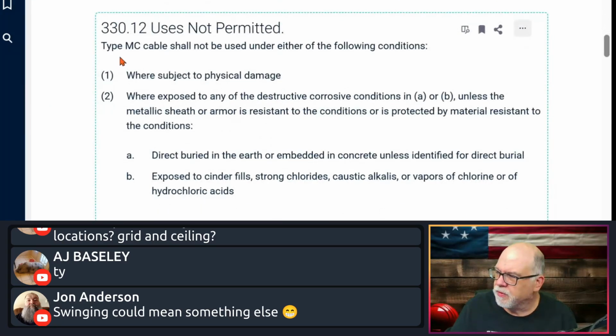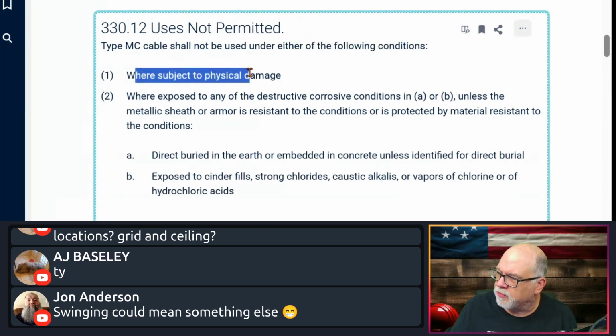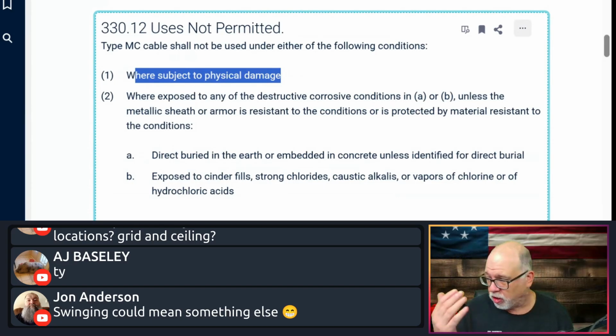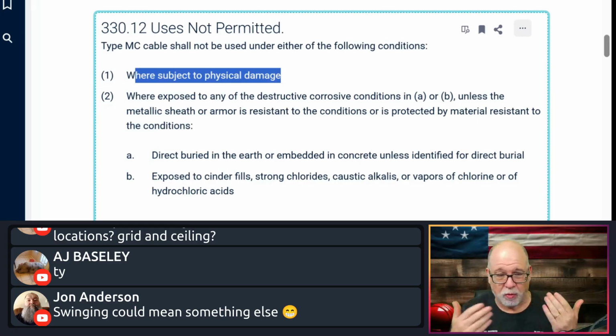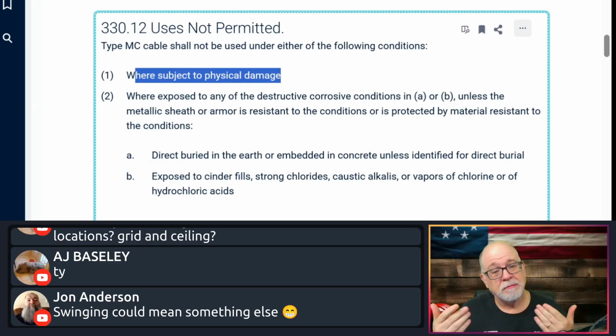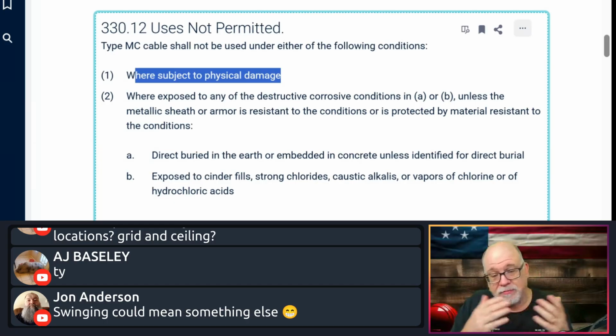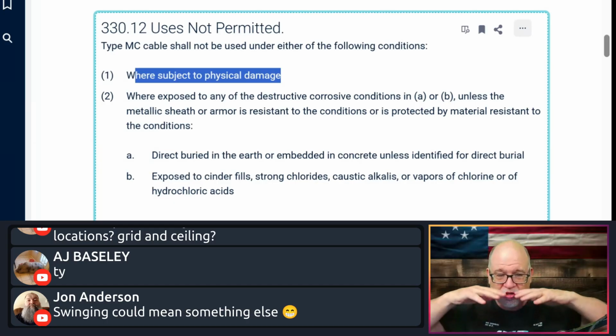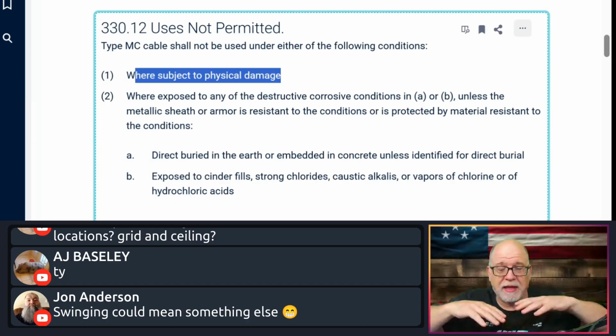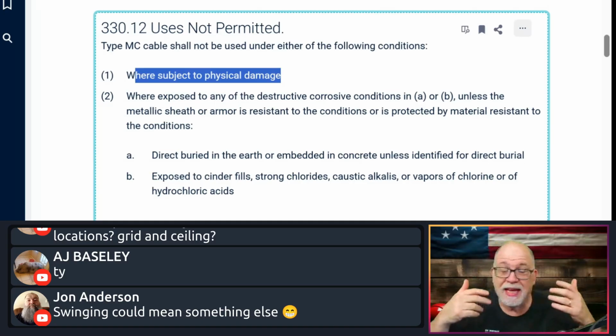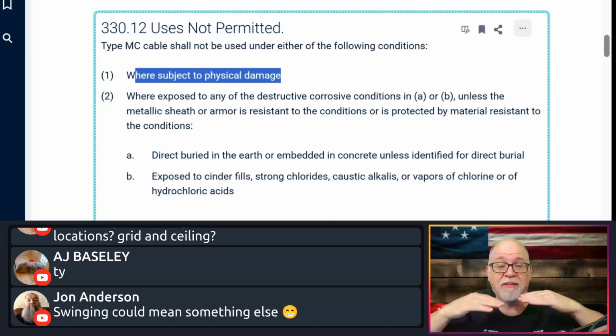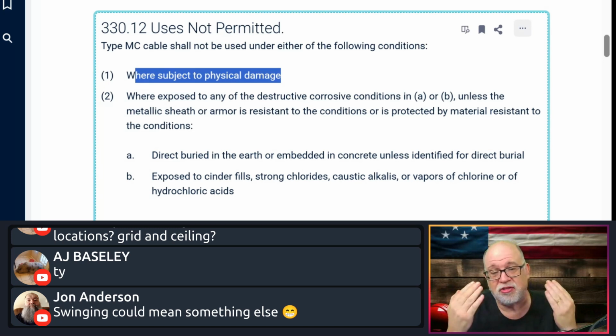Uses not permitted. MC cable shall not be used under either of the following conditions. Number one, where subject to physical damage. This is one thing that people blow and don't understand, whether it's aluminum armor or it's steel armor. Doesn't matter. Okay? Pick your poison. Whichever one you want. Steel, okay? Aluminum is lighter. They both have to meet the exact same crush and impact test. So you might think, well, steel is stronger than aluminum. It may be, but they both have to meet the exact same test. So again, it's your choice. Okay?